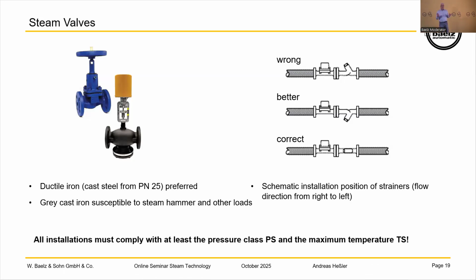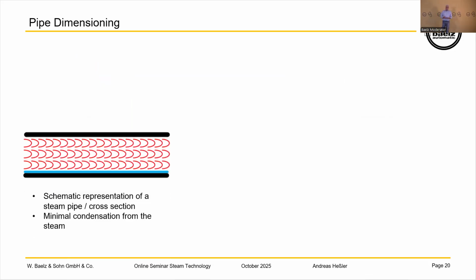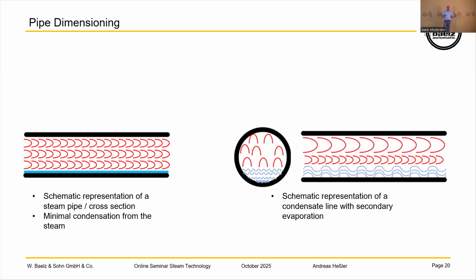The installation must be completely rated for the least pressure, the PS class, and the maximum TS of the steam. Let's go to the pipe dimension. Here on the left picture, you see a schematic of piping when you have some condensate in the steam pipe. So you have a little small condensate on the bottom of the pipe. On the right side, you will have a schematic picture. You see when we have flashing or a lot of high water influence in there, mostly when you have a pressure reduction of hot steam condensate to a lower pressure, then you have a steam water mixture inside the pipe. So this is much more critical for the steam pipe than the normal condensate.